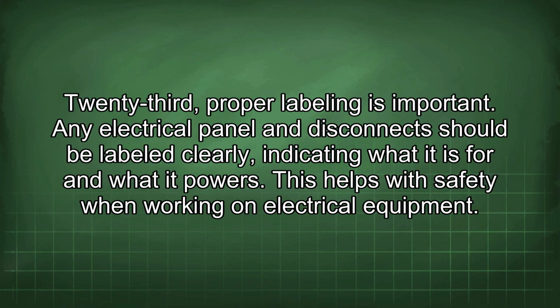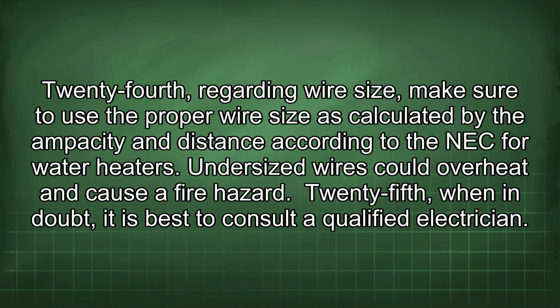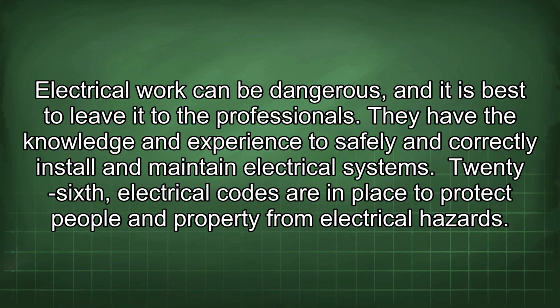23rd, proper labeling is important. Any electrical panel and disconnect should be labeled clearly, indicating what it is for and what it powers. This helps with safety when working on electrical equipment. 24th, regarding wire size, make sure to use the proper wire size as calculated by the ampacity and distance according to the NEC for water heaters. Undersized wires could overheat and cause a fire hazard. 25th, when in doubt, it is best to consult a qualified electrician. Electrical work can be dangerous, and it is best to leave it to the professionals. They have the knowledge and experience to safely and correctly install and maintain electrical systems.